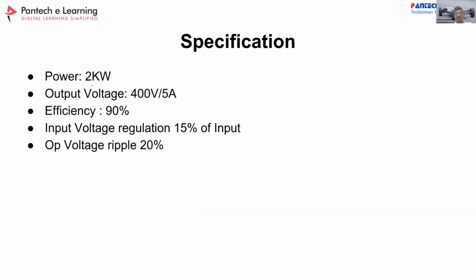We have selected a 2 kilowatt converter rating, with output voltage 400 volt and 5 ampere as the typical rating. Efficiency we are trying to keep at 90%. We could go up to 98%, but then you should select all components as ideal components, and getting such components is very difficult.